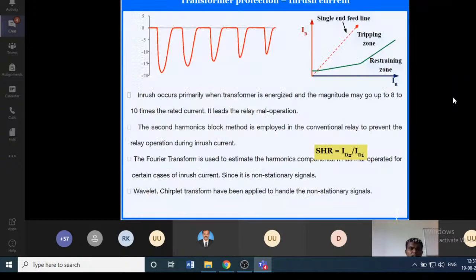Usually inrush current occurs when a transformer is energized. The magnitude may go up to 8 to 10 times the rated current, so obviously it is going to lead to maloperation. The second harmonic blocking method is used in the conventional relay to prevent the relay operation.